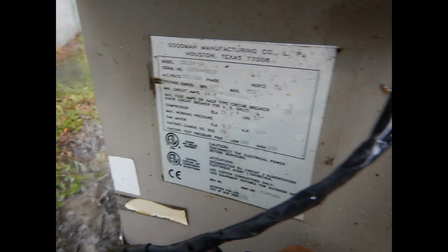Imagine if you're one of these people photographing the condenser and air handling unit but not getting your eyes on the coils, and you report that the unit is 20 years old, and that's where it ends. Folks, over the last 17 years or so, I can't tell you how many times the outside manufacturer's information was not representative of what was going on inside.